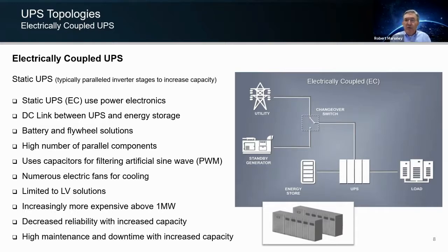Generally these UPSs use a large amount of internally parallel components. We call these multi-module systems to get to somewhat larger sizes. As soon as you get above 500 kilowatts, they're usually using multiple modules to make a UPS module, okay? They're going to have a lot of capacitors, a lot of fans for cooling those power electronics. And they're really confined to the low voltage area. So they're really available in 480 volts, and when you get really small, down to the 208. As you get into larger systems, it presents the challenges of multi-module systems. That also, we believe, decreases your reliability and increases your maintenance and downtime requirements.